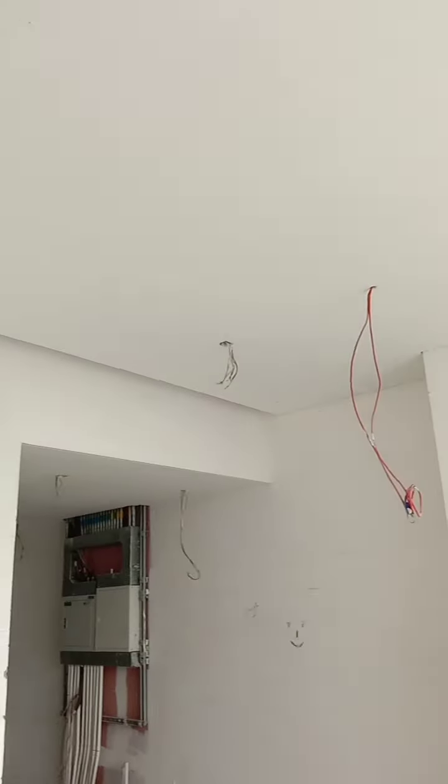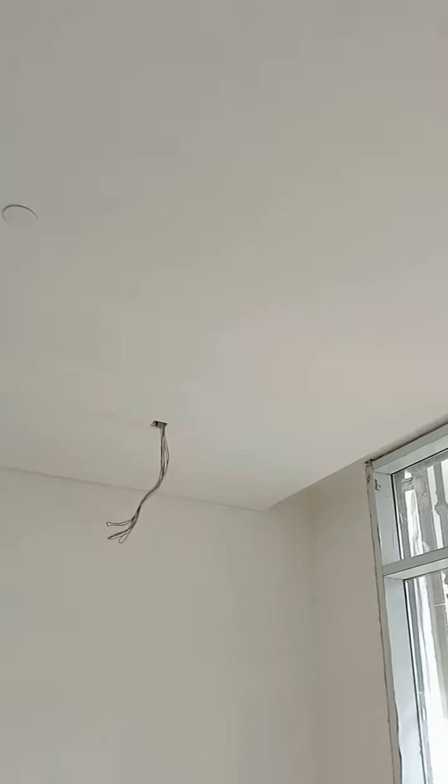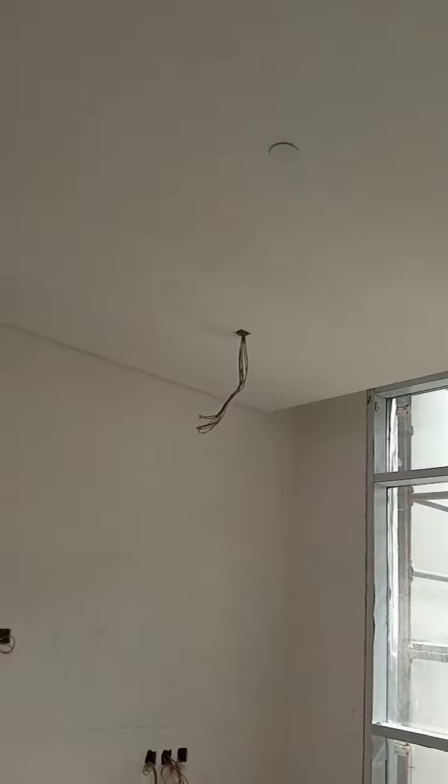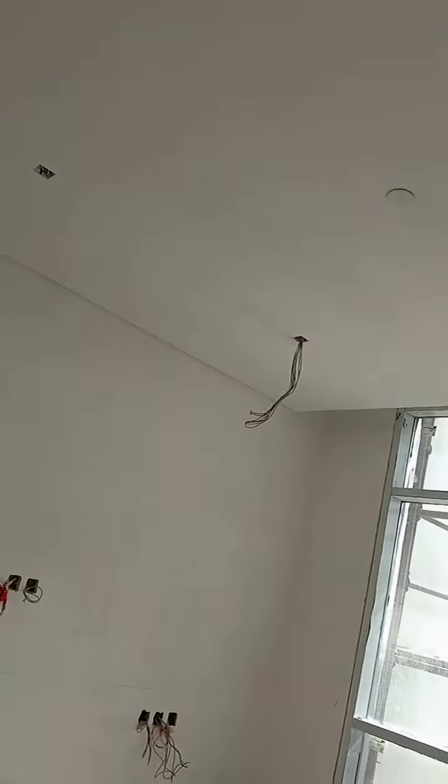Before proceeding with the final fixture, we have to make sure that our RCP, the reflected ceiling plan, is approved and it is the latest before we can proceed. So all the marking has been done based on the latest and approved RCP, like you can see. Once we get clearance from the civil department or the architectural department, we can now proceed with our final fixtures. Then we will raise another inspection to make sure that what we've done is as per the requirement, as per the project specification as well, which is very important.